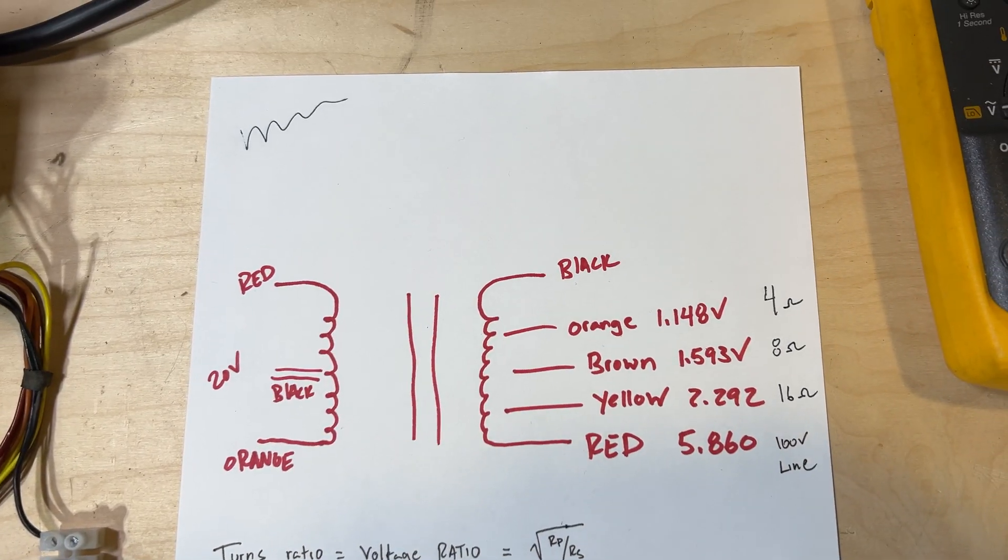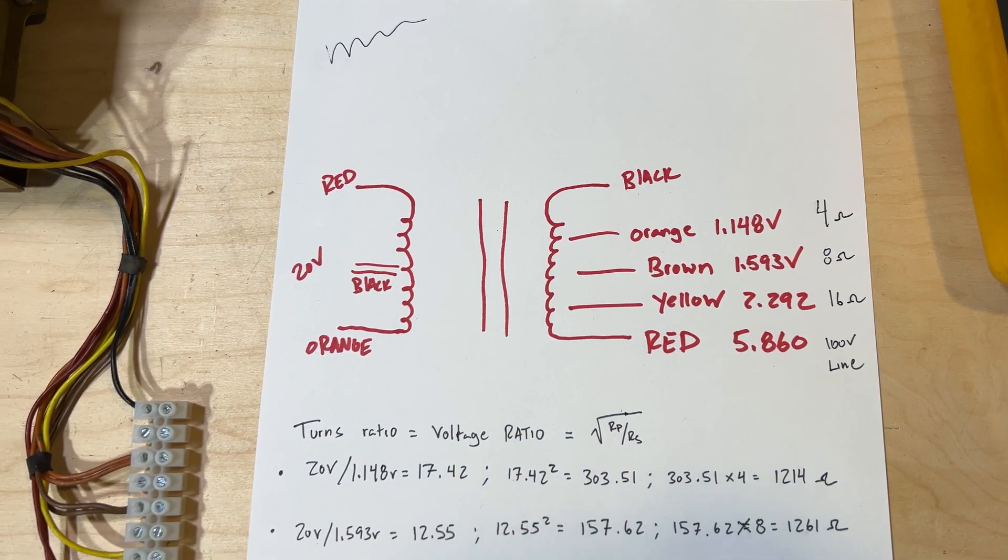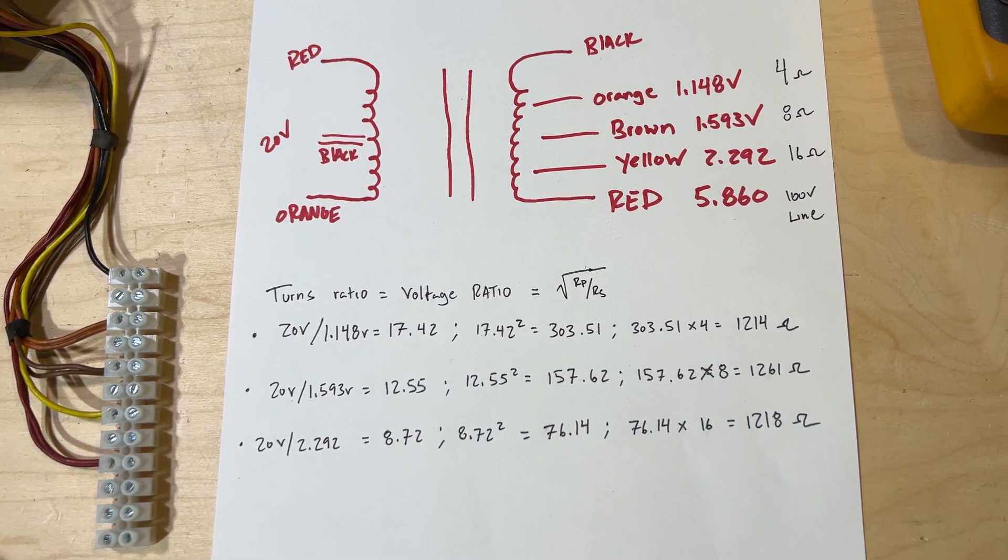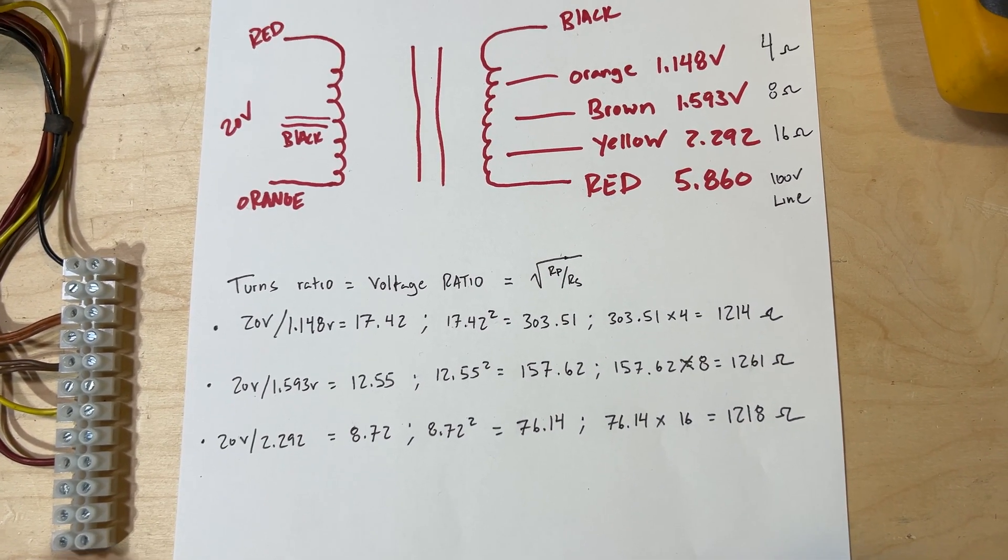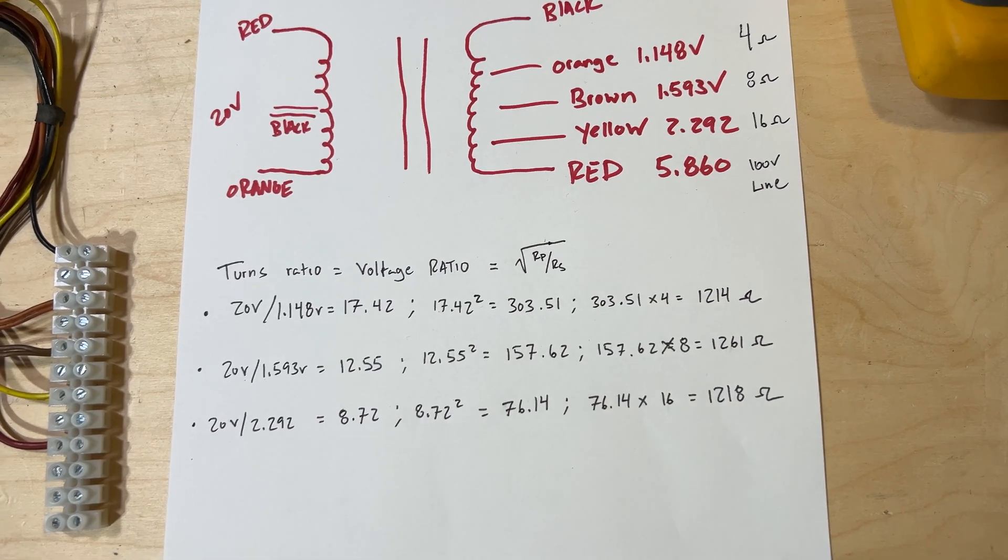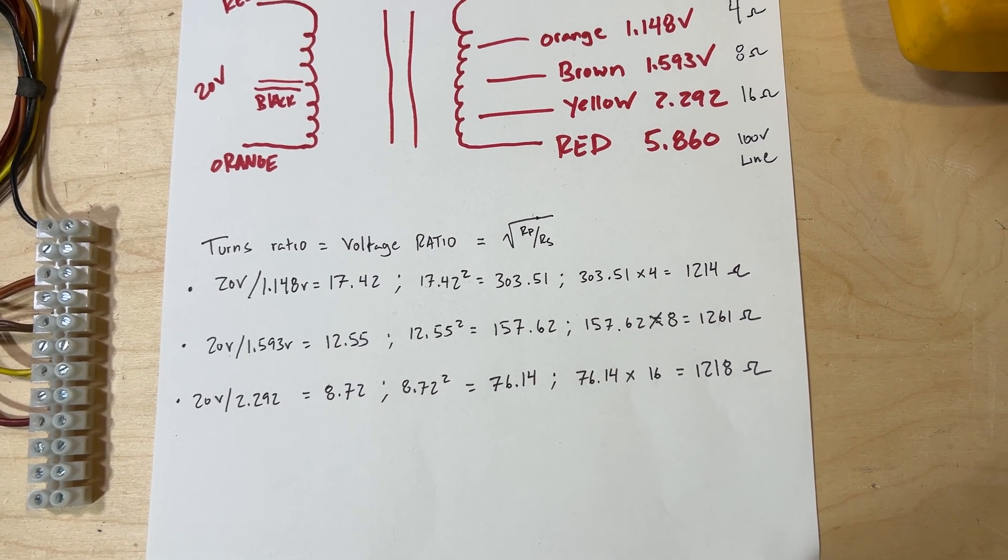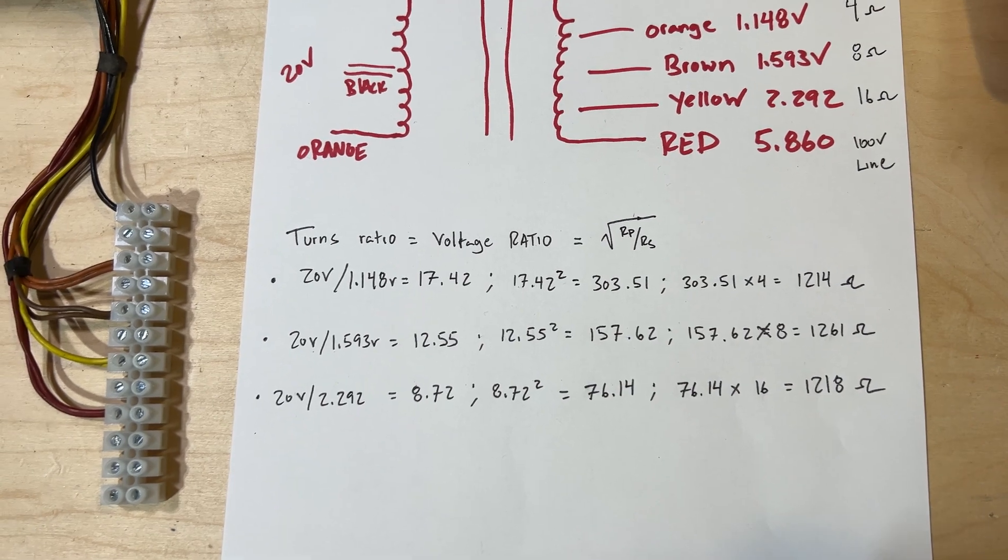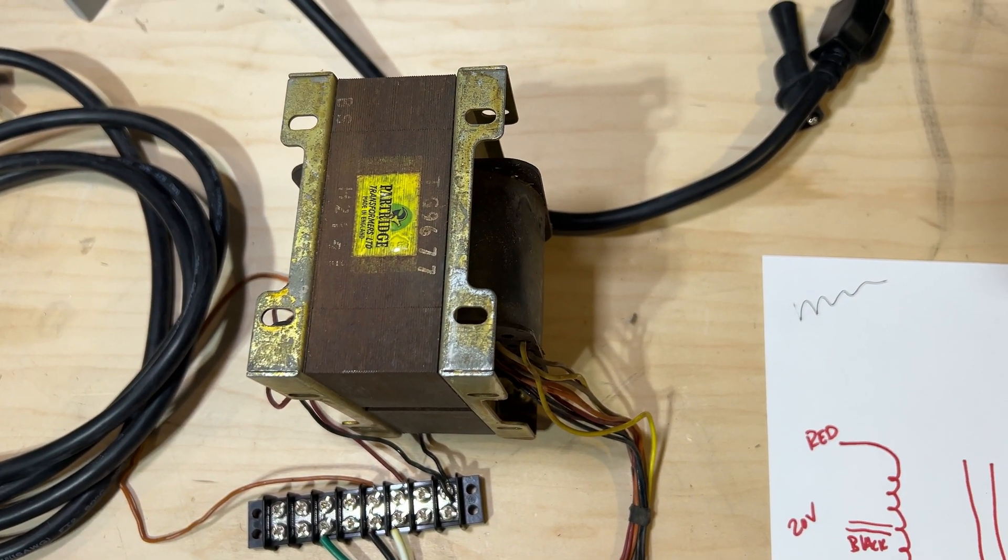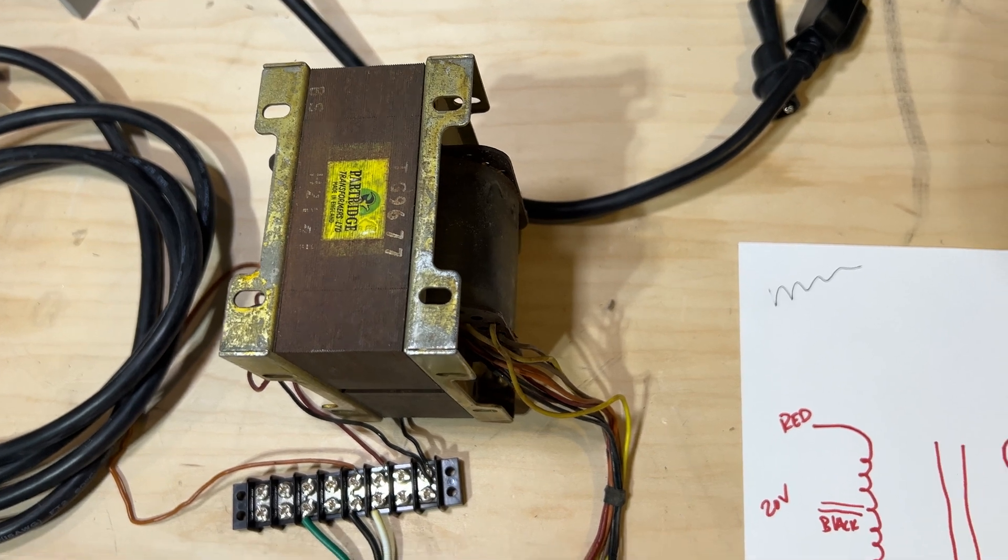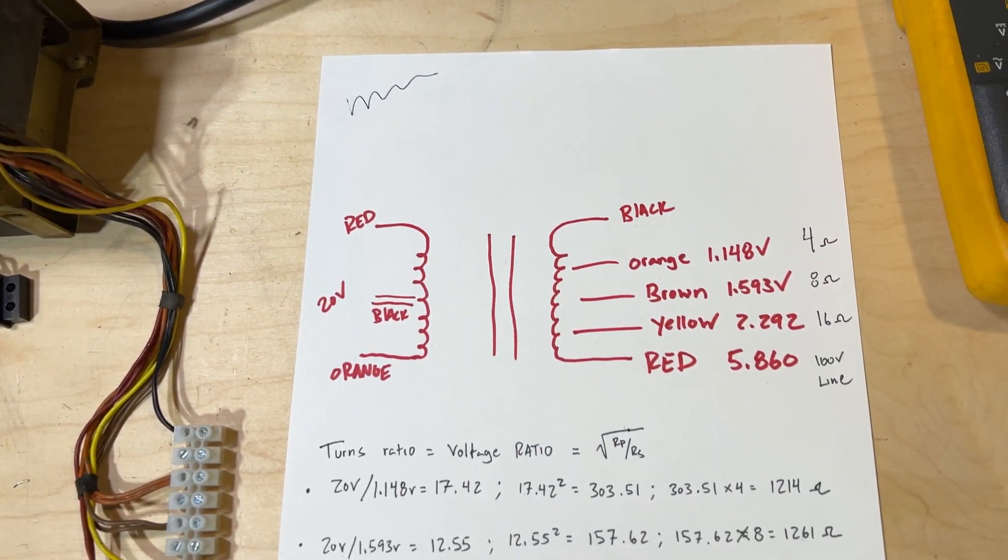I may do some further tests. I may ramp up the voltage off the variac, something closer to what we might see in the amp, just to see if that number gets closer to the ideal 1,700 ohms or so. But I think we can say that this transformer is ready to go, ready to rock.